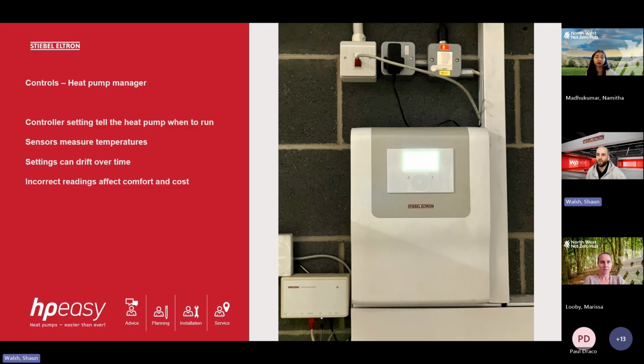You can have reduced output from the machine if they've turned it too low. It might not be outputting correctly. But also your energy use can increase. If someone turns up domestic hot water to 55, 60 degrees, and it's doing that every day, that's going to increase energy costs massively compared to when you would normally have it at, say, 48 degrees, for example.